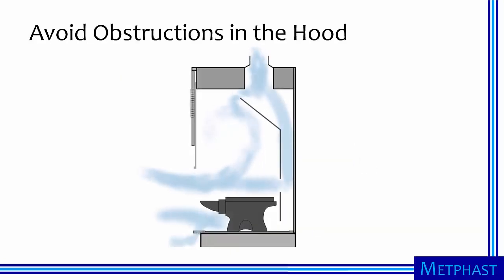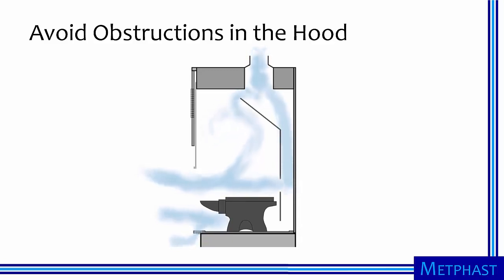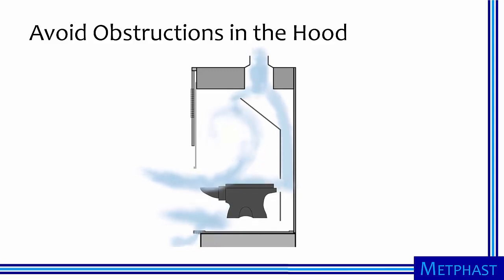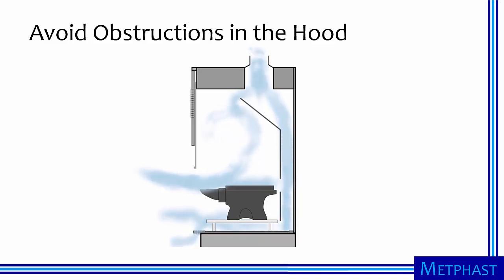Avoid placing unnecessary items in the fume hood for storage, as these items can obstruct the proper airflow from the front of the hood to the rear slots. Use a small table or shelf to elevate necessary items and allow airflow to pass underneath. Never place anything on top of the airfoil or directly in front of the rear slots.